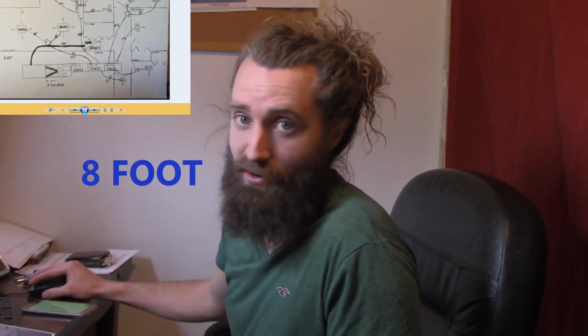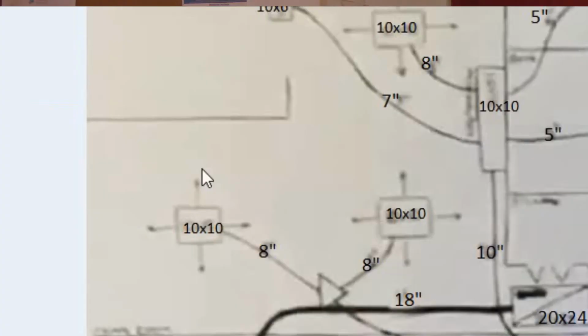If you're not feeding, let's say this 10 by 10 supply over here in the living room, if you're not feeding that with 600 feet per minute, you're not going to get the 8-foot throw that it is designed at, okay? You might get 3 feet of throw. Likewise with the kitchen. It looks like this kitchen, he's got it just kind of sitting here on this wall, and he's throwing the air across the kitchen against the far wall.